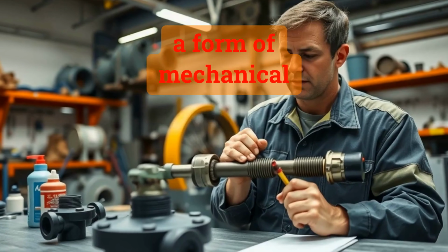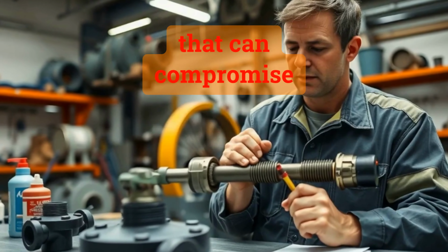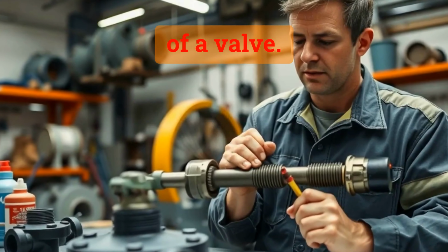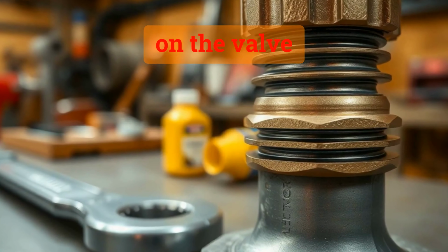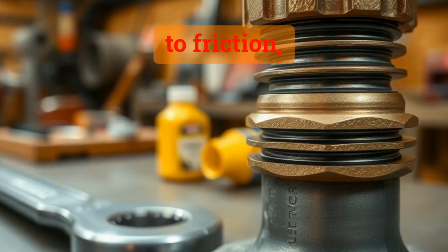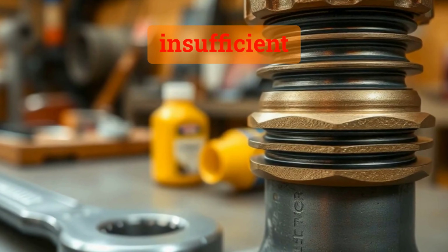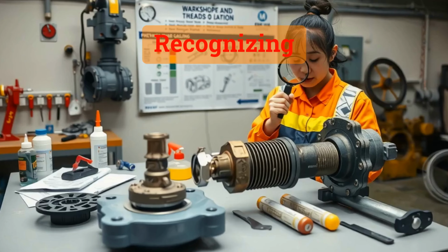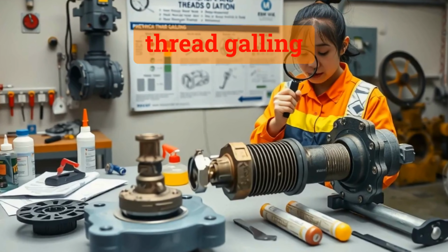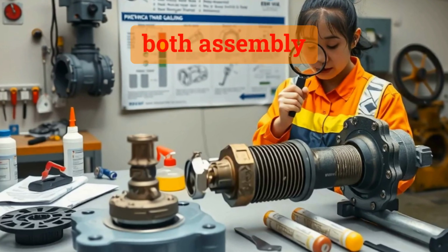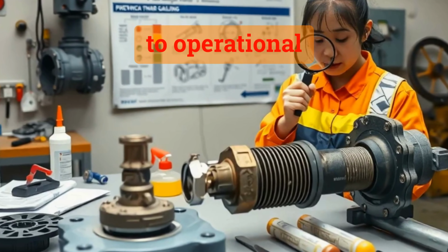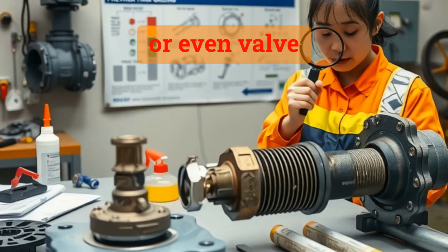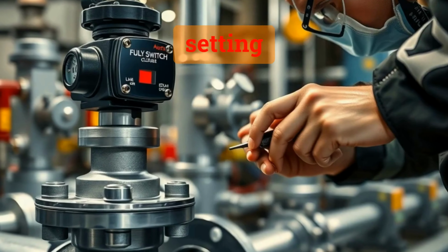Stem thread galling is a form of mechanical wear that can compromise the reliability of a valve. Galling occurs when the threads on the valve stem are damaged due to friction, often exacerbated by insufficient lubrication. Recognizing and preventing stem thread galling is essential during both assembly and maintenance, as it can lead to operational difficulties or even valve failure. Limit switch setting is a key aspect of automated valve systems.